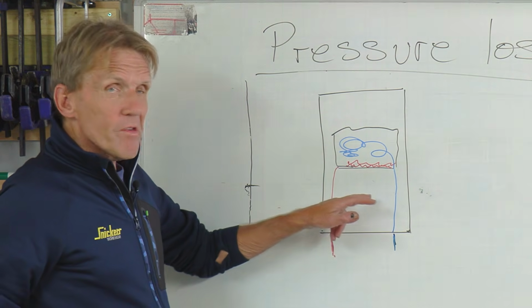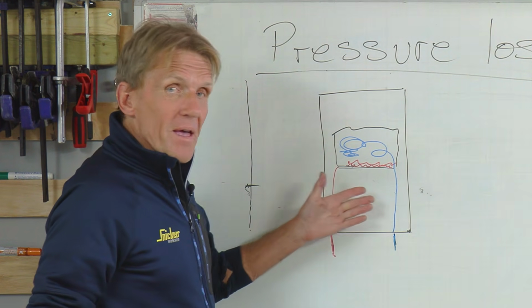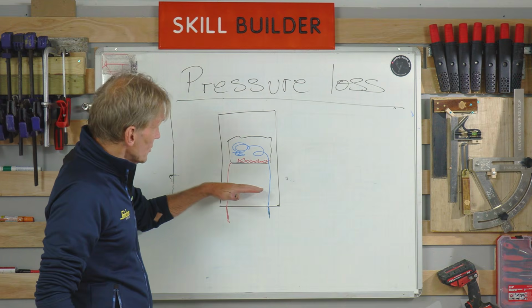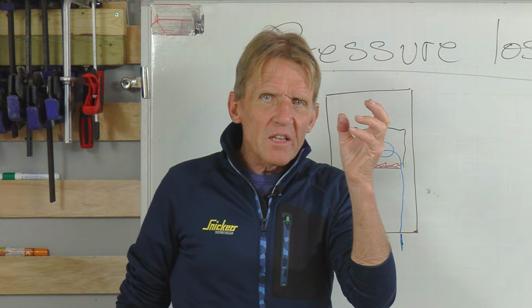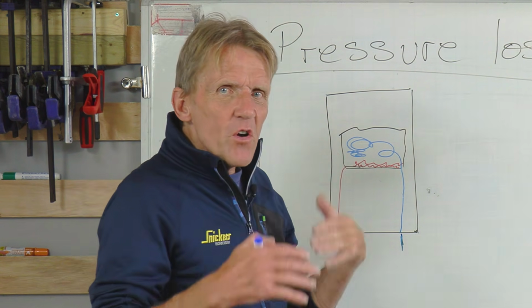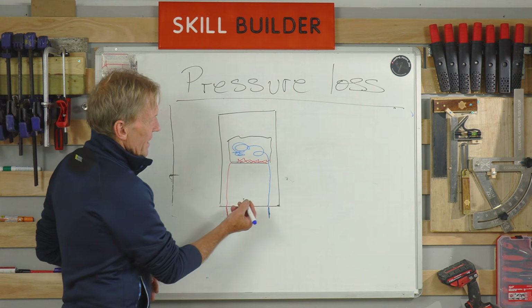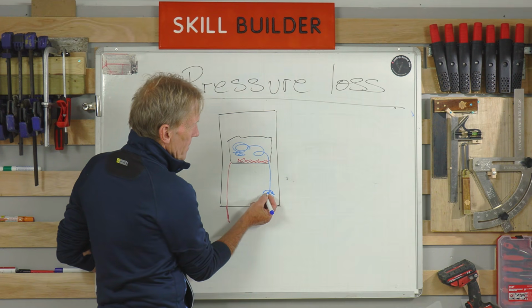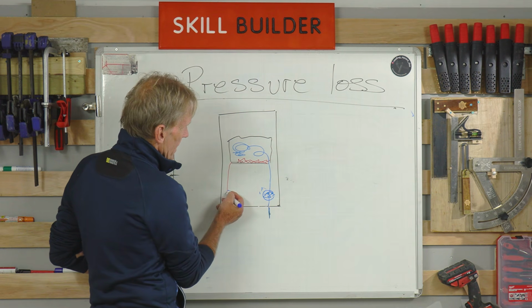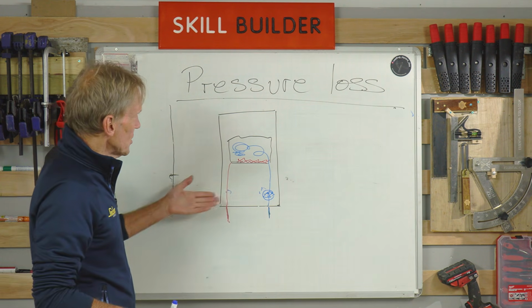Now inside that boiler there are a lot of connections, and you may think that if it's leaking inside the boiler you would see some evidence of it. So when he or she takes the cover off and has a look inside, they will be looking for any kind of nasty stains, any green staining, verdigris building up around that, anywhere that looks like there might be a leaking connection on a pipe. Maybe down by where the pump is, there may be a little connection down there. There may be a connection here, which is just leaking a tiny little bit of water, which isn't being noticed.